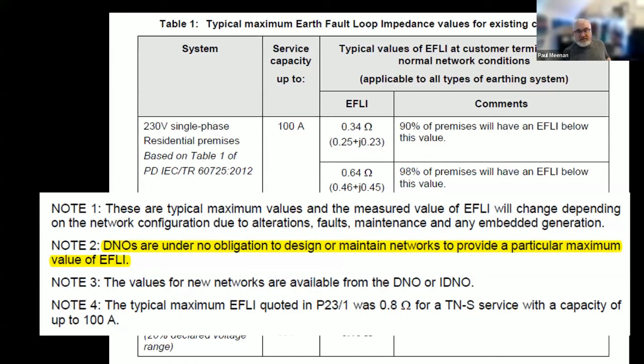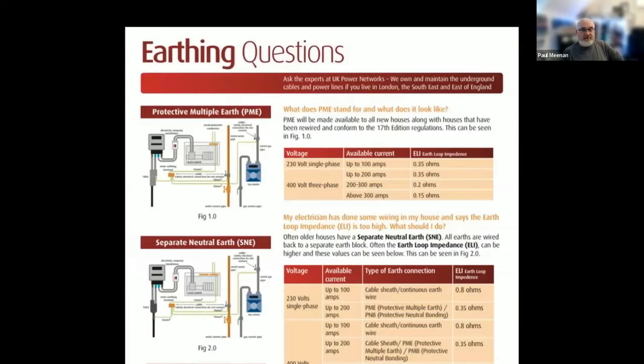One of the more scary points in the UK is note 2: distribution network operators are under no obligation to design or maintain networks to provide a particular maximum value of earth loop impedance. However, under our Electricity Safety, Quality and Continuity Regulations, they are obliged to maintain the earthing. So a little bit of contradiction there, and it makes it very grey. Always an interesting debate with your network supplier, for sure. But some companies will publish very simple guides to earth loop impedance maximum values, 0.35, depending on the level of energy, 0.8, their standard values for the different earthing systems.